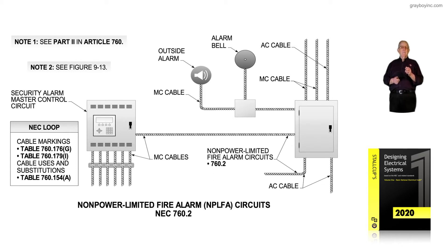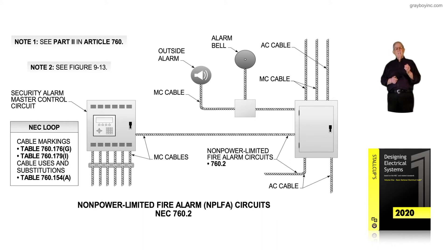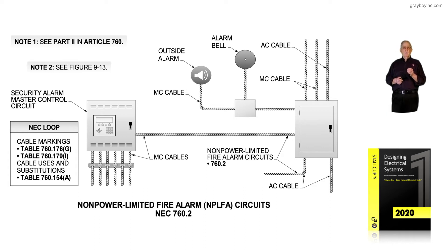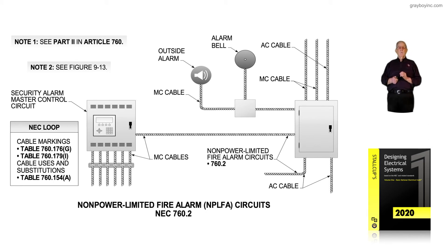Notice the cables used to run to these individual devices to sound the alarm for fire, smoke, different things that might occur — water, maybe a sprinkler system goes off. Notice in the NEC loop to the left of the illustration, cable markings — we can find those cable markings in table 760.176G, cable marking 760.179I, and cable uses and substitution type cables in 760.154A, which we could use instead of the above cables.